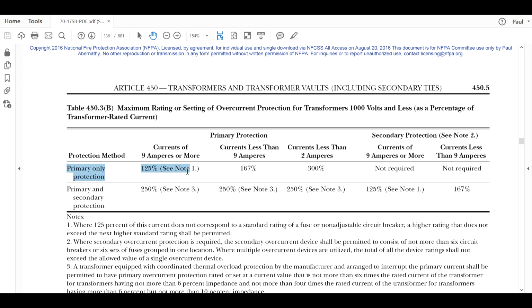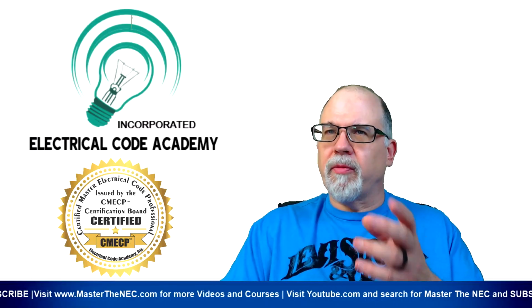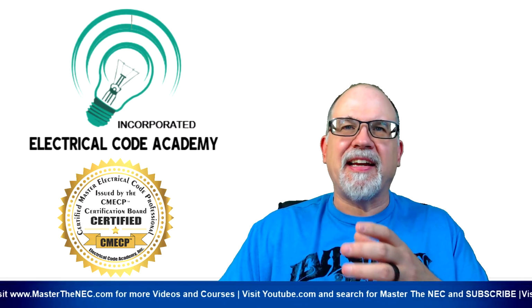When somebody sees this, they think, well, when can I have primary-only protection and not require secondary protection? This is, again, of the transformer. That's what we're talking about. Well, as long as that primary overcurrent protective device doesn't exceed 125%, and yes, Note 1 does apply, which is if it doesn't correspond, you go up to the next non-adjustable circuit breaker or fuse rating. If that's the case, then I don't need any secondary protection for that transformer. Okay? Now, that is very true. Just remember that that has nothing to do with protecting the secondary conductors.